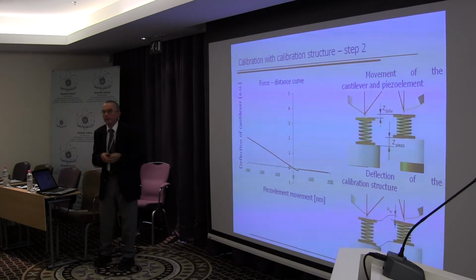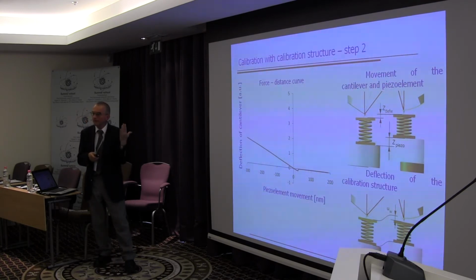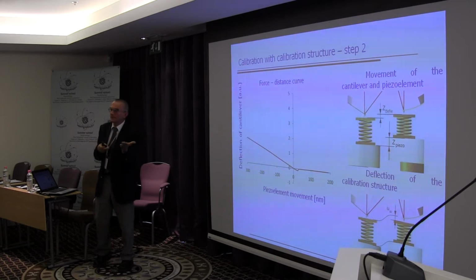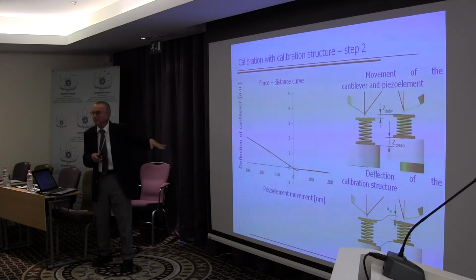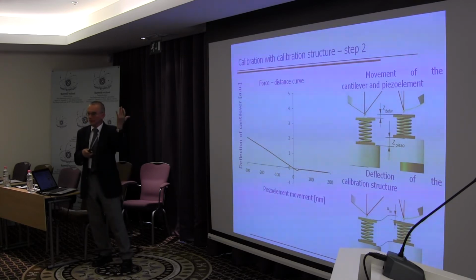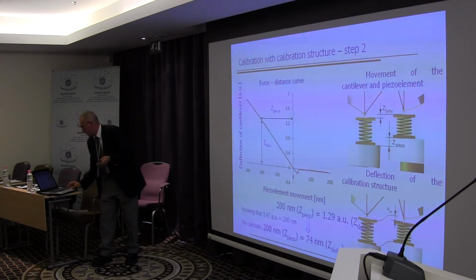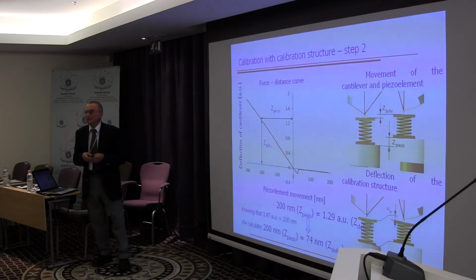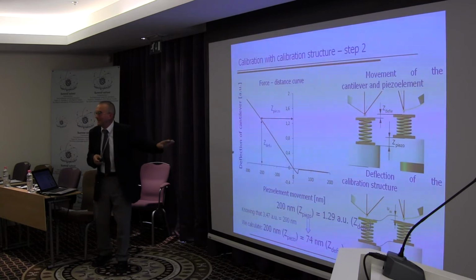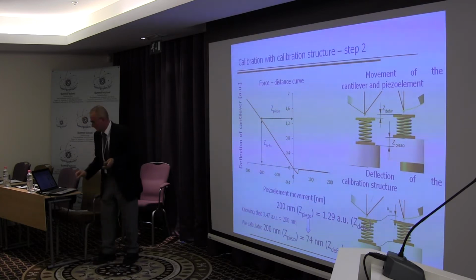Okay, and after that, if we have a spring with well-defined stiffness, we introduce this inside the system between the cantilever and the very stiff substrate, and we do a force distance curve again. And because we know the stiffness, and we know the deformation, because it is the displacement of the scanner in the vertical direction, with very simple equations we can estimate exactly the stiffness of our cantilever. I will not introduce you to this detail because it will take some time. It is not important, but this is the simple idea.